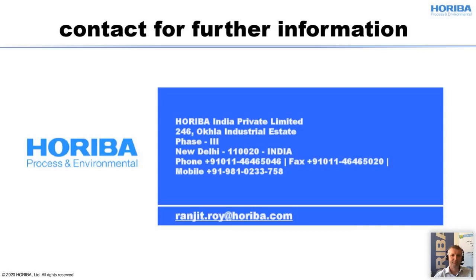Next question: for CEMS extractive type, as per CPCB India, which type of oxygen analyzer is required, inbuilt or separate? You can have both kinds of oxygen analyzer, inbuilt as well as separate. It all depends upon your location, and whether you are already using an oxygen analyzer or not. If you are using an oxygen analyzer, then why invest in another one? But if you are not using an oxygen analyzer, it is better to have an inbuilt analyzer, with which you are also measuring SO2, NOx and other parameters.